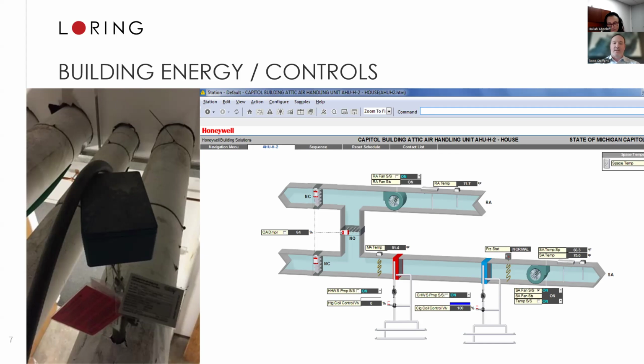So in this example, we can see an air handler, and it's pulling points in. Each of those individual blocks is a different input or output point. And we would think of an input point as what a temperature sensor is telling the computer, and an output point as the computer telling the machine to do either one action or another, turn a fan on, modulate a cooling or a heating valve, things like that. And it's important to both have that and make sure it's reliable.